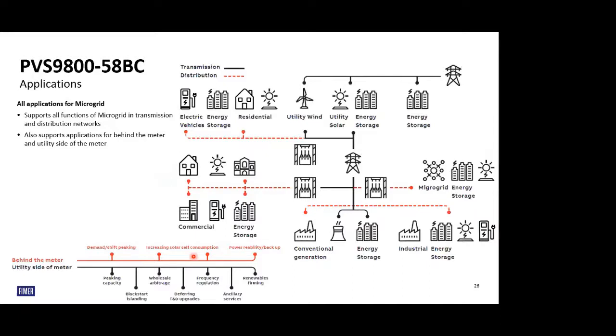And when you have it on the utility side of the meter, for the DISCOMs or the PGCIL and such transmission companies, then you can use it for peaking capacity, like what happened on the duck curve. You can use certain storage to shave off those peaks. Then we can also island a system and start immediately. We need not wait for 15 hours like when that event happened, and that islanding will happen by itself very easily. Then we can have wholesale arbitrage: if there is some excess generation, we can store it and dispatch it to other places. Such logic could be written, and without upgrading the infrastructure, we can use the existing assets to their maximum. We will see how we do it in the further slides.